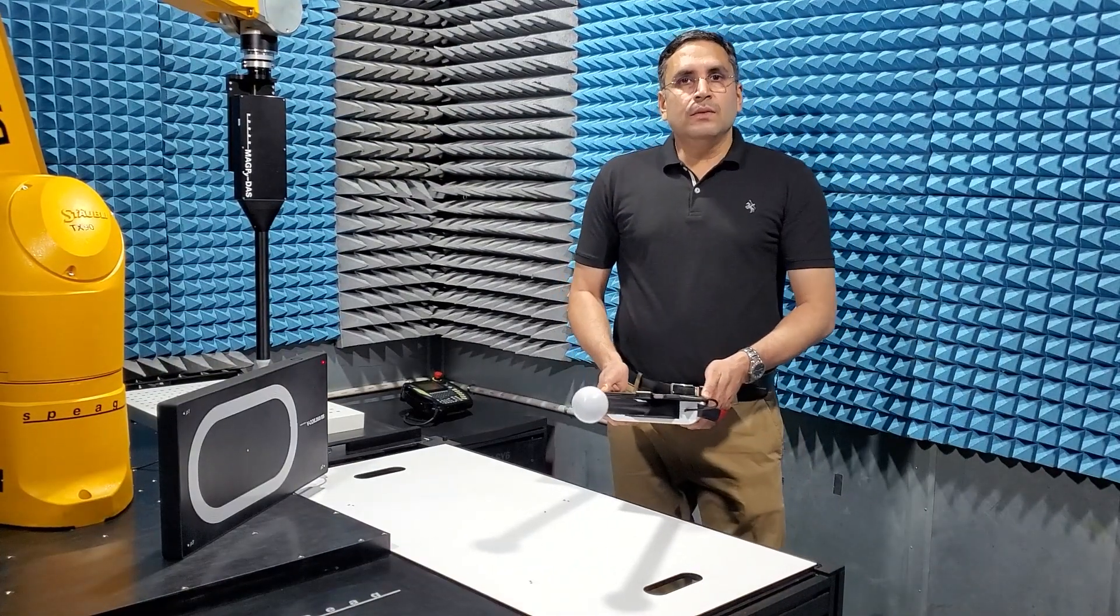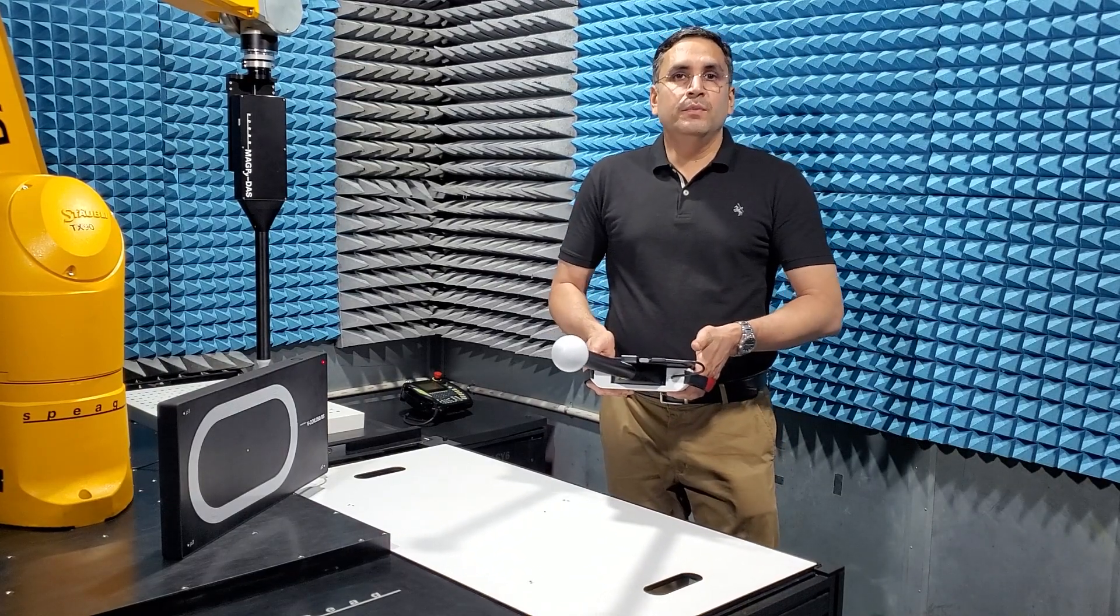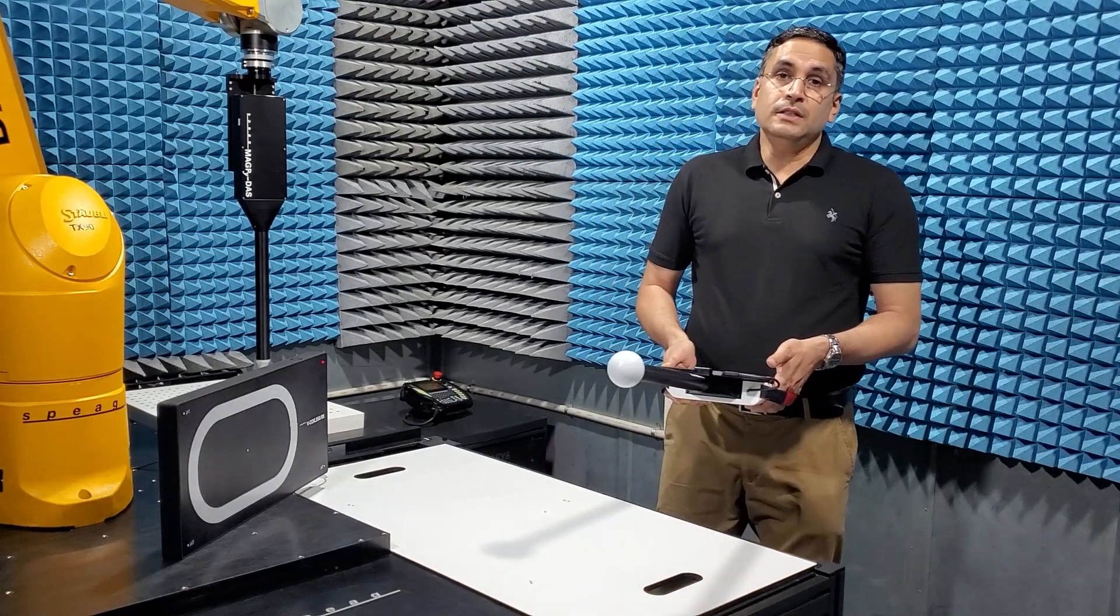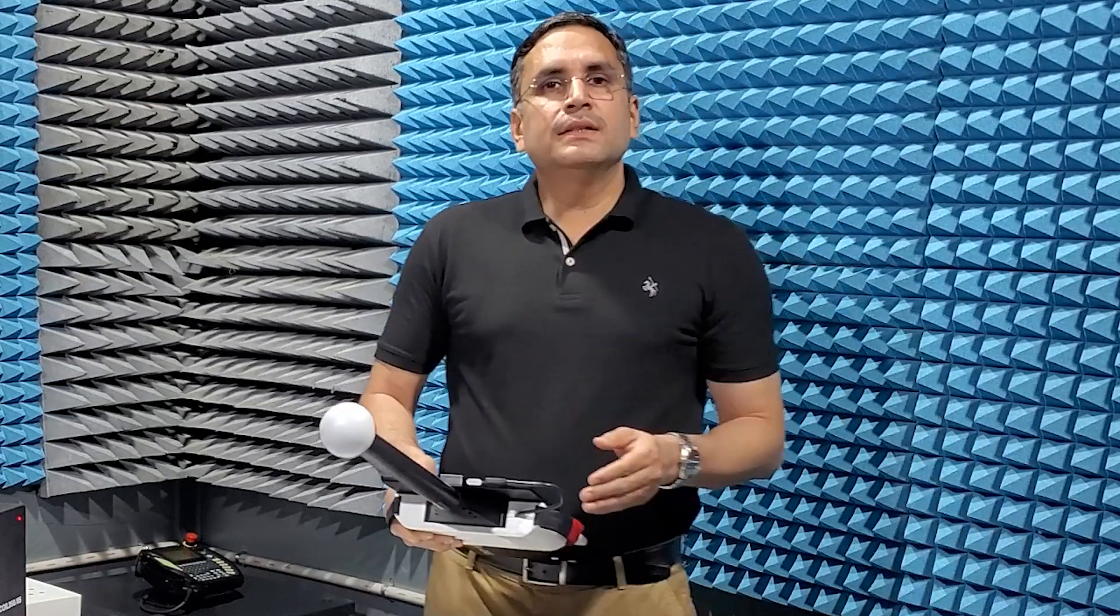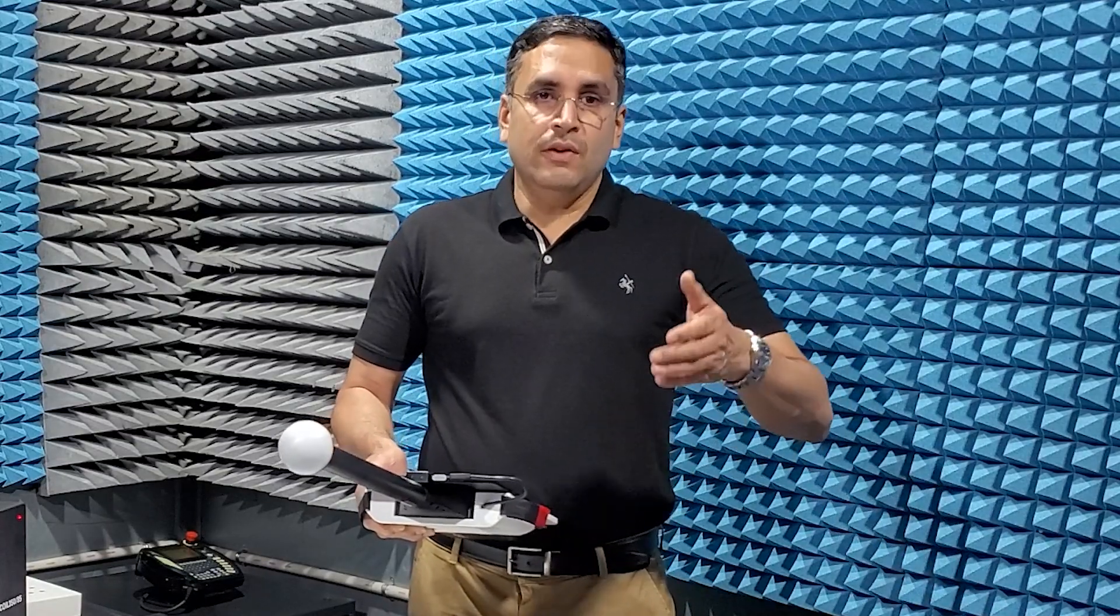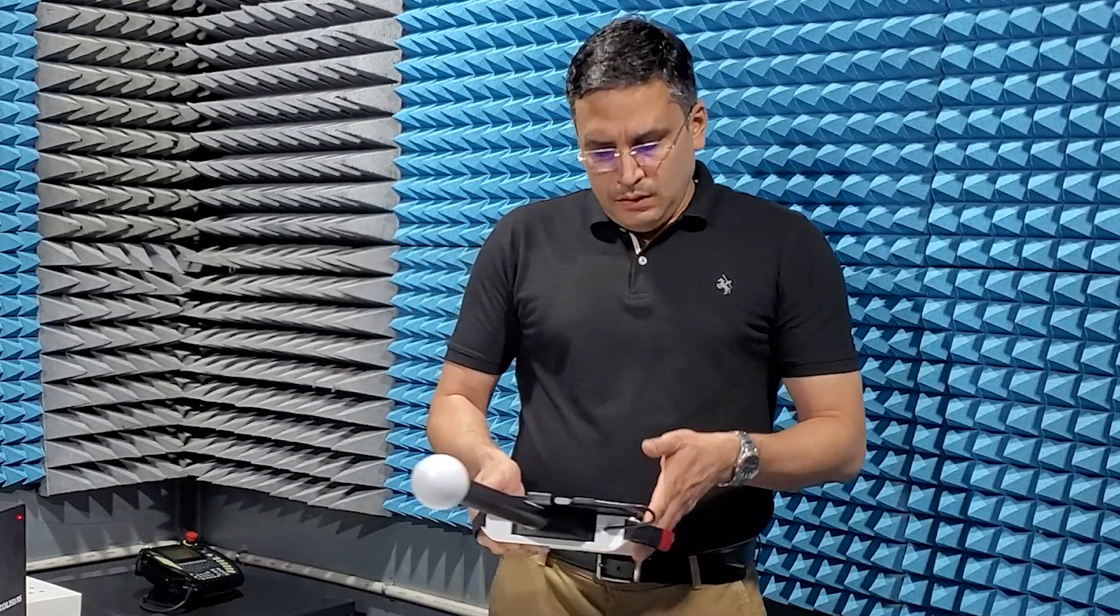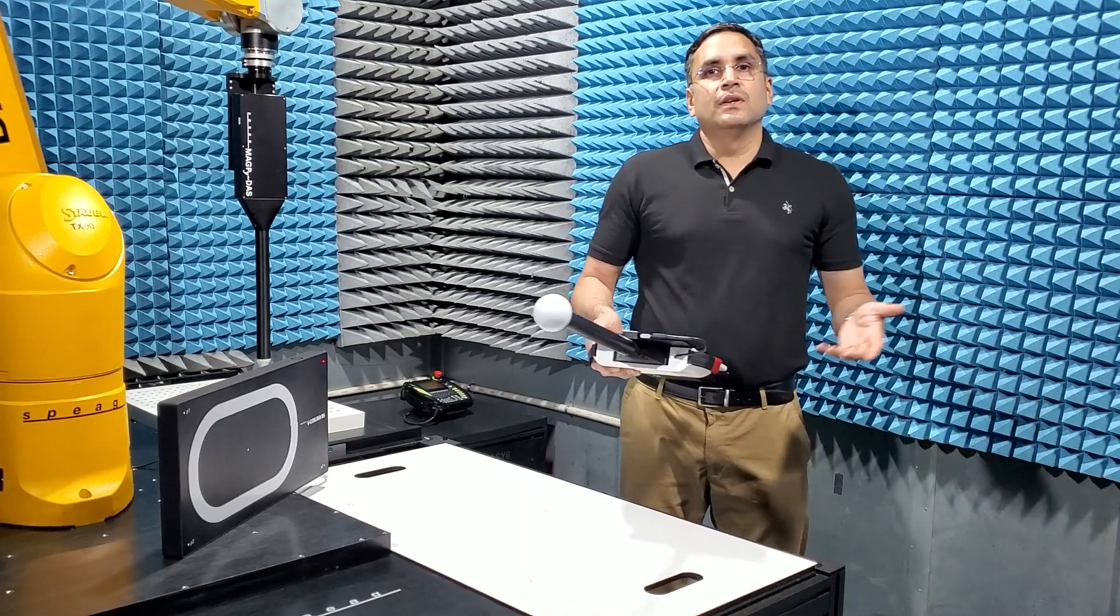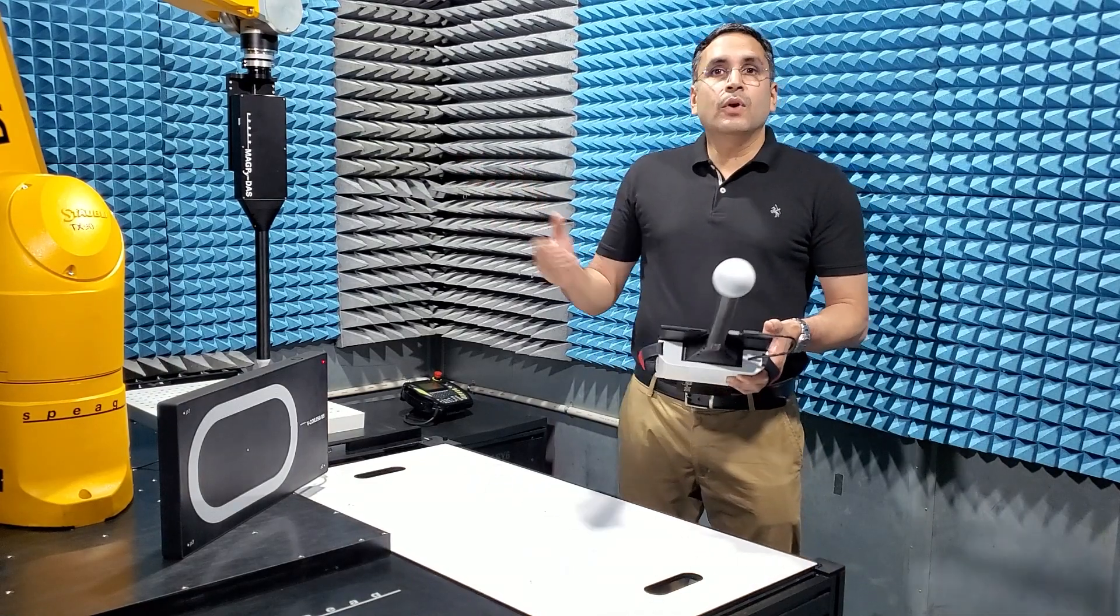The MAGPy system is unique in its application as it measures not only the field components of the E and H fields, but also their gradients. These measurements allow the user to test compliance by comparing directly with the basic restrictions instead of the reference levels, and thus offers several dB advantages due to reduction in overestimation built into the reference levels. The system is intuitive, easy to use, and yet offers the unmatched precision which has become synonymous with any SPEAG product.